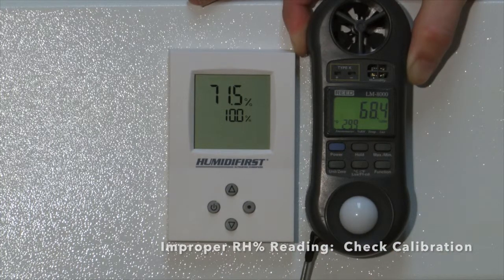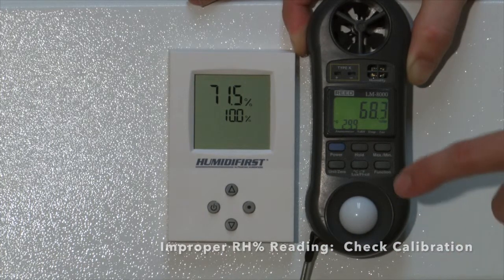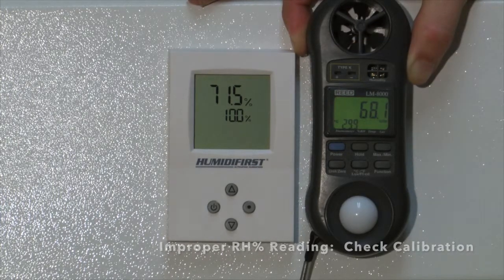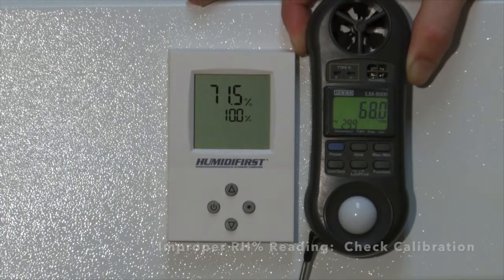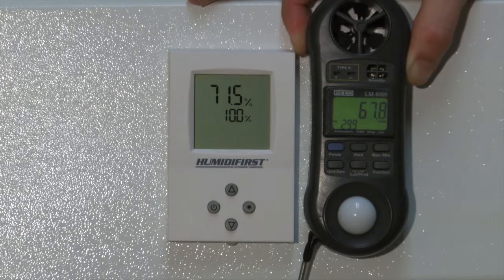Turning the humidistat back on, you will see our reading of 68.3 and 71.5, much closer. Note that 2 relative humidity sensors will almost always read slightly off. This is just the nature of relative humidity sensors.